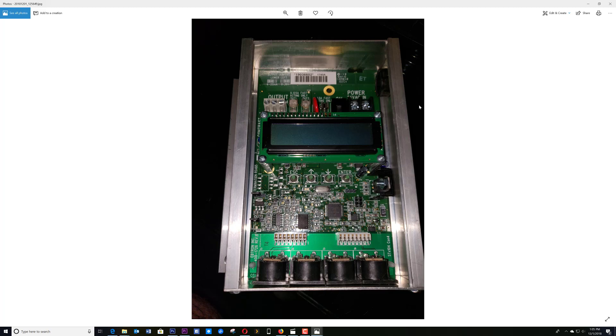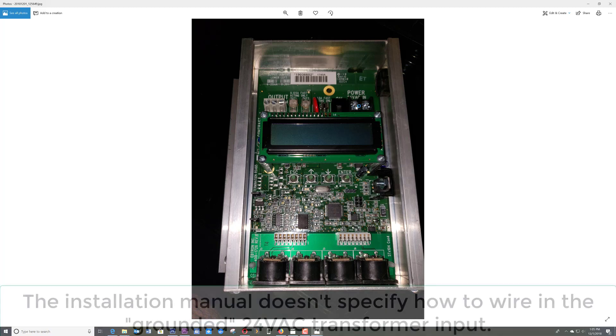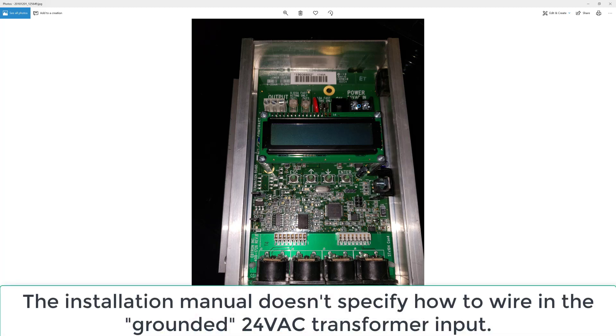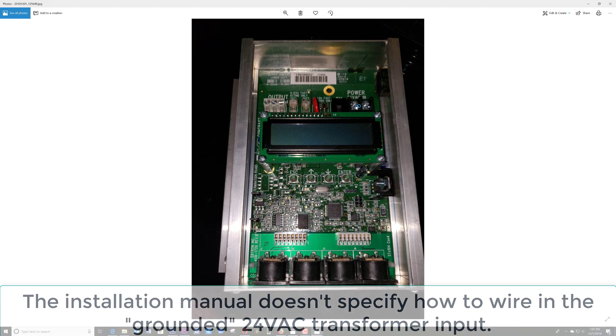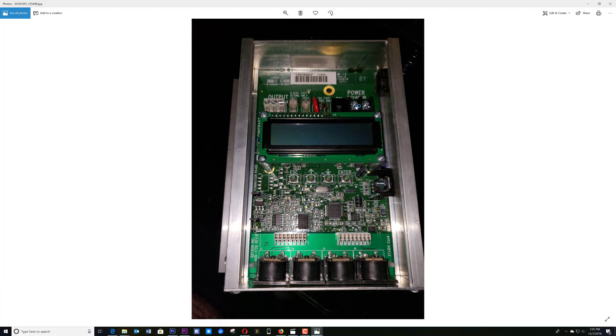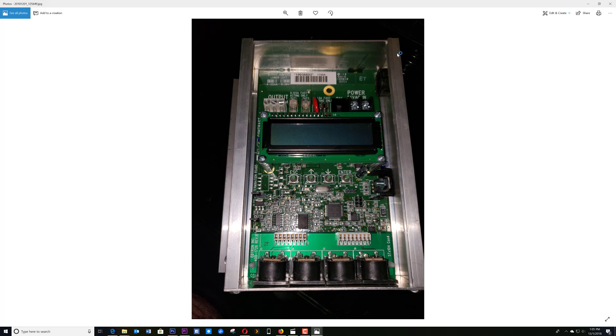The only thing I'm thinking is that with one side of the transformer grounded, maybe you need to put the hot on the L1 and the grounded one on L2. I don't know. When I put it back, I'm not going to take any chances using the transformer they used, which had other circuits tied to it and did ground one. And I'm going to use an isolated transformer when I put this back in there. So obviously the first controller they put in blew up for the same reason. Some sort of ground loop or something in it coming back in and fried those chips.